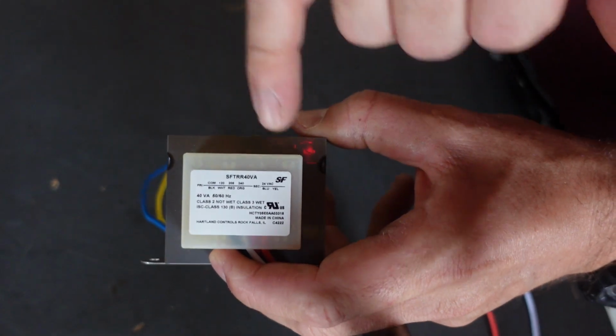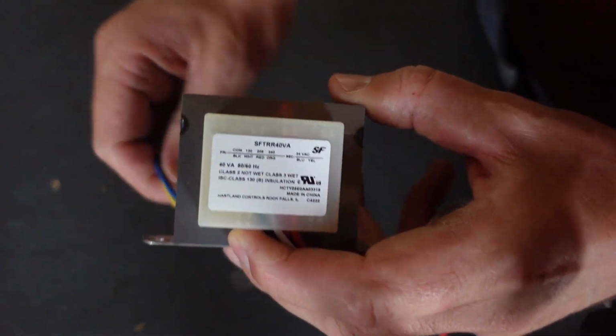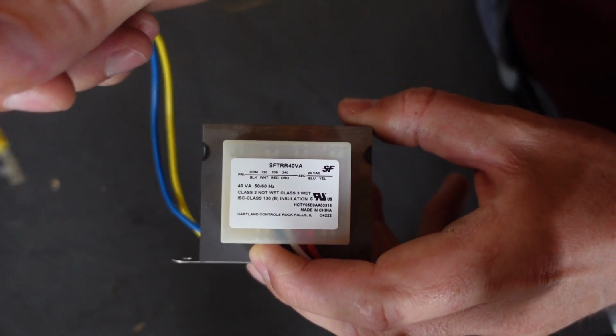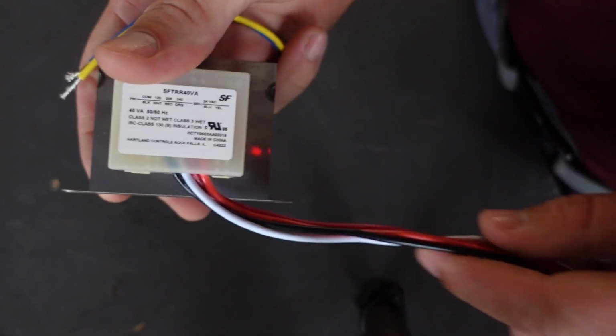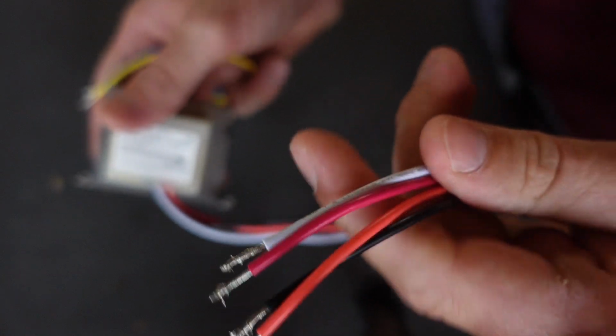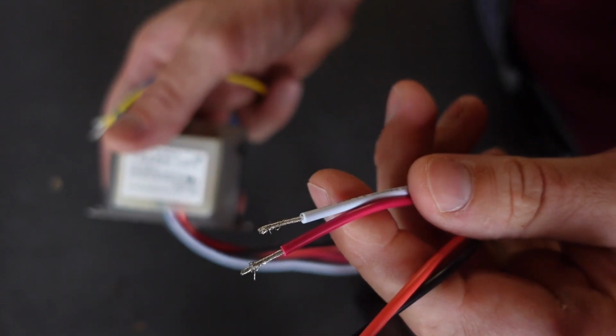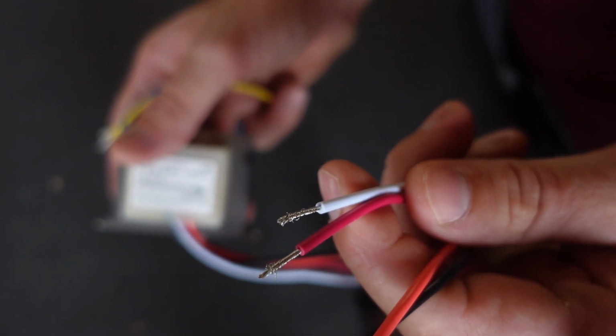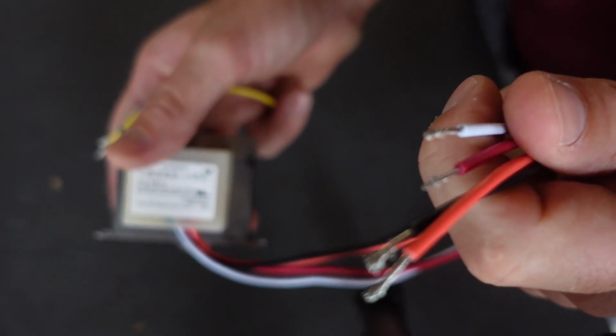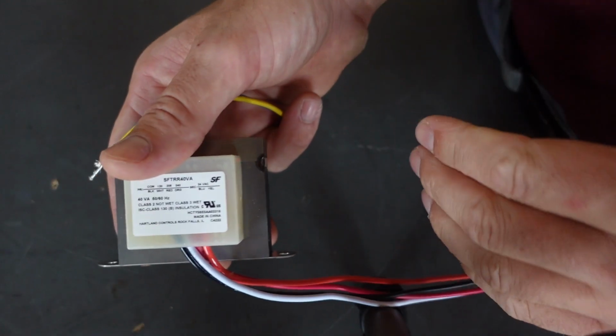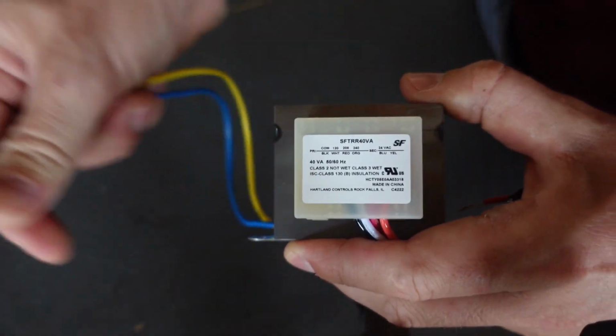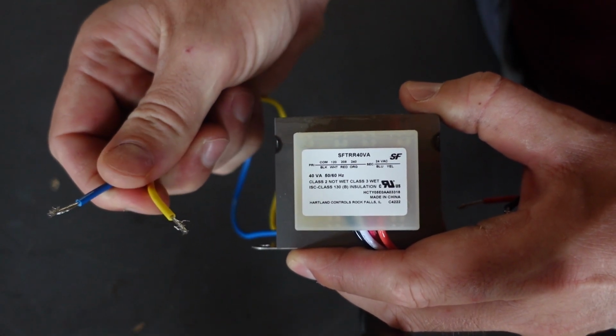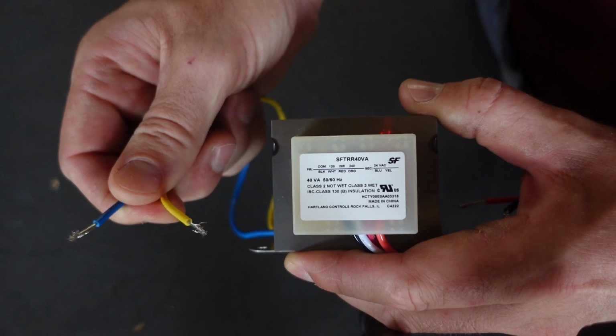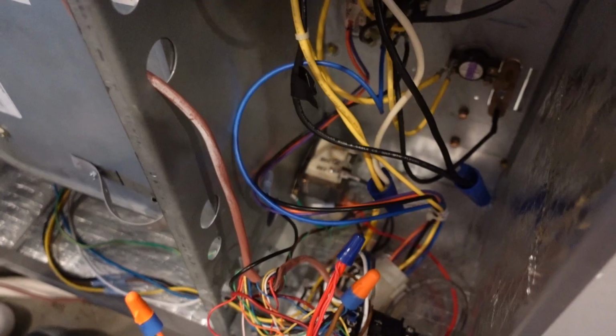Okay, so what we're looking at here is an actual low voltage transformer, but it's important to understand that this is where all your low voltage in a system originates. This particular one is a universal, so we've got several different wires here. We're not focused on the high voltage side coming in. We will focus on that in a different video, but this is where your low voltage comes out. So you've got a common and a hot, and this is where all of your low voltage begins.